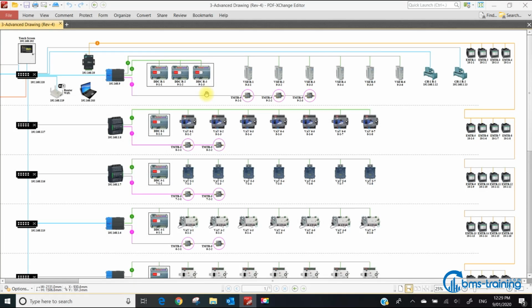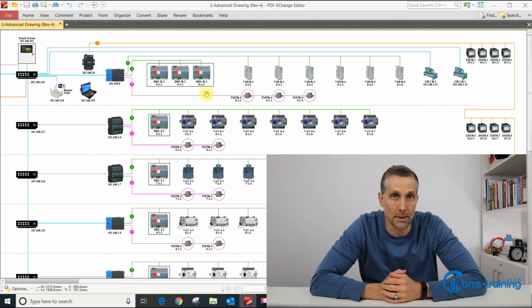In the early 2000s, the last 20 years, it's generally been the BMS scanning for collecting data, sending out commands, time schedules, starting, stopping equipment. So you might have a building management system, an energy management system, and a building analytics package. All three of them are now polling through the network controllers down the sub-networks to collect information. So in this example here, where there's 4 electric meters on the end, you could have the energy management system every 15 minutes coming down and polling all the way down that sub-network. Collect 1, collect 2, collect 3, collect 4. That's the kilowatt hours every 15 minutes.